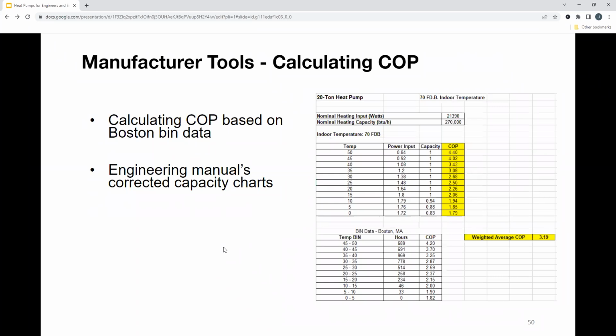The last tool I wanted to share with you, it's pretty straightforward, but it does calculate COP. And it calculates this average COP, right? So this is just an Excel document that I put together where you can go into the engineering manual and look up your corrected capacities. So for this example, I have a 20-ton heat pump right here, and we're looking at the indoor temperature of 70 degrees Fahrenheit, right? So you go to the graph, you enter in your nominal heating input, right? And power, and then your nominal heating capacity associated with that.